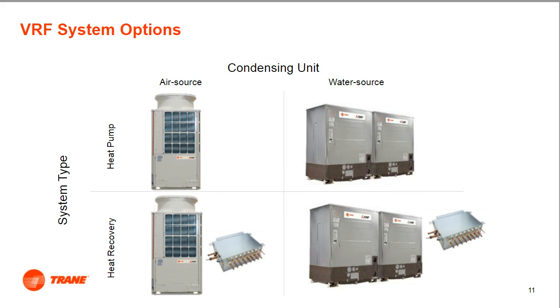Here, we have a simple matrix that represents the basic VRF system options. The heating and cooling unit can be either air source or water source. They are often also referred to as condensing units. While air source units are located outdoors, water source units are located inside the building. The system can be a heat pump or, as you see below, a heat recovery system. This is where the level of zone control flexibility is determined. Let's take a closer look at the system options.